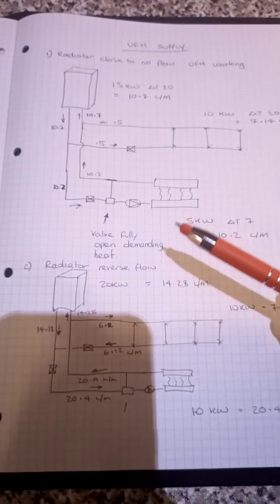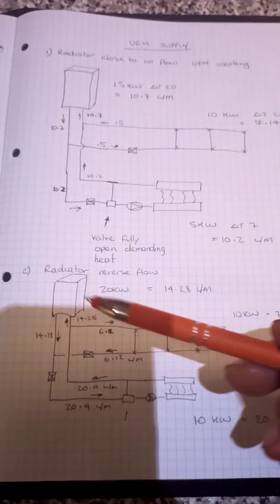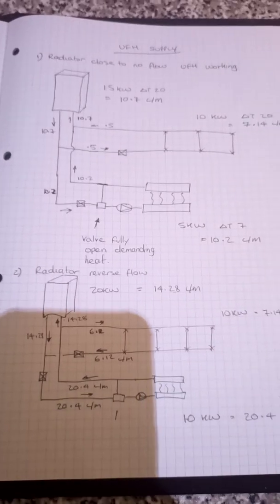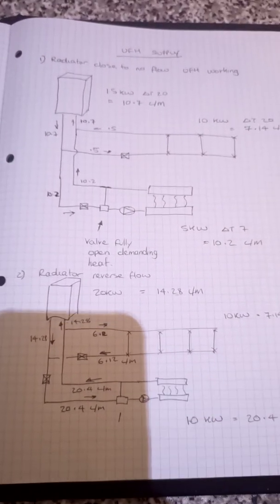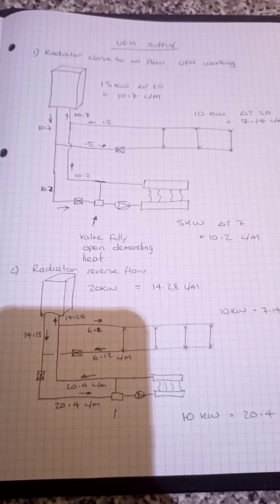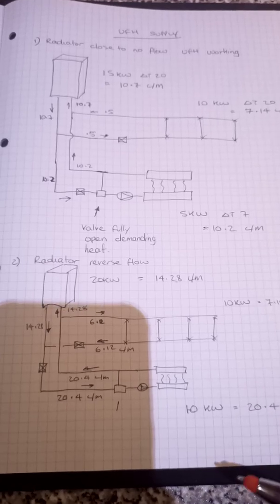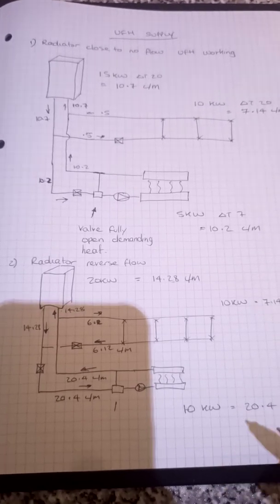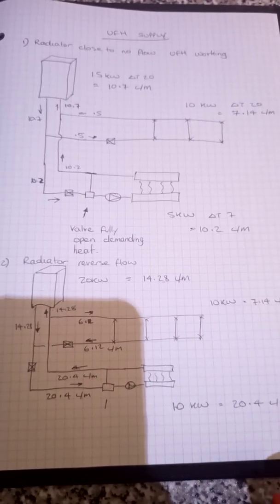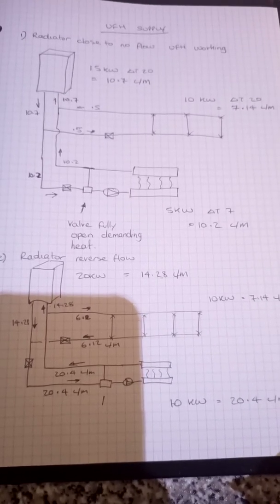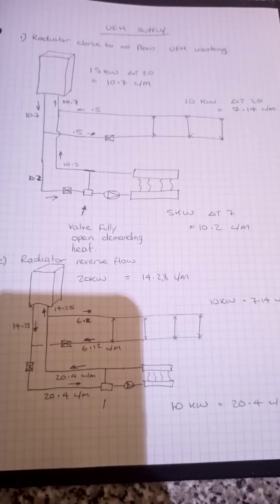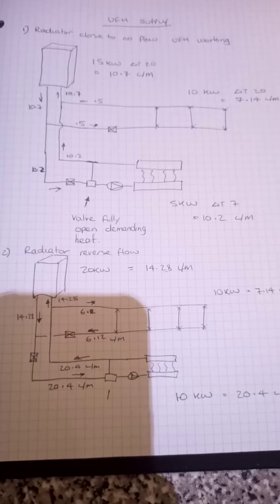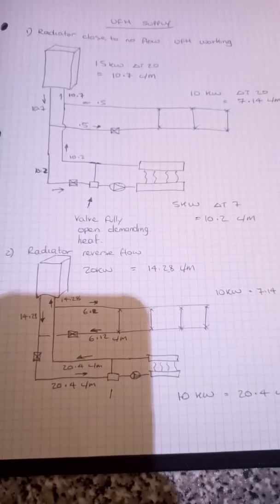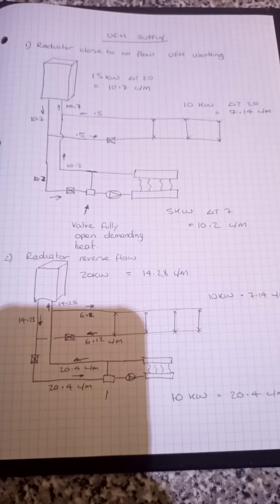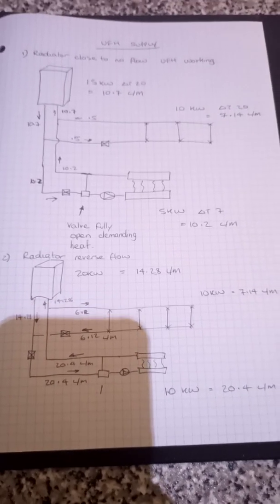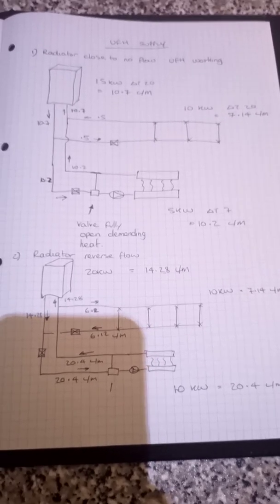Now, these interactions run on a scale. So as temperatures change and as the system loads change and valves change and TRVs change, all of these flow rates will vary. They will almost never be correct on a system that does not have hydraulic separation. You can do the maths as many ways as you like, but you can only get the correct answer at one condition unless you have a low loss header. Or hydraulic separation rather can be any of the forms that I've discussed. So I hope that helps. Should explain everything. There's a lot more to this than just this short video covers, but this is the key point.